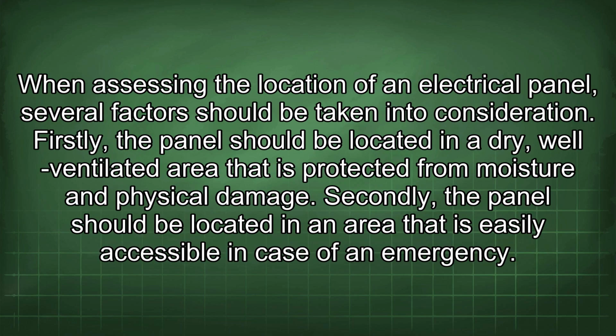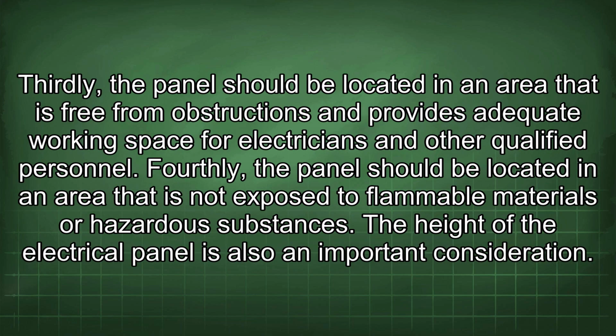When assessing the location of an electrical panel, several factors should be taken into consideration. Firstly, the panel should be located in a dry, well-ventilated area that is protected from moisture and physical damage. Secondly, the panel should be located in an area that is easily accessible in case of an emergency. Thirdly, the panel should be located in an area that is free from obstructions and provides adequate working space for electricians and other qualified personnel. Fourthly, the panel should be located in an area that is not exposed to flammable materials or hazardous substances.